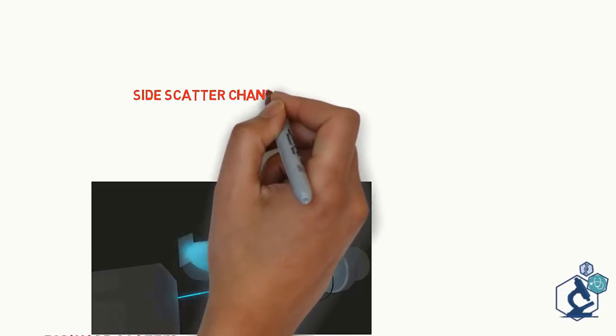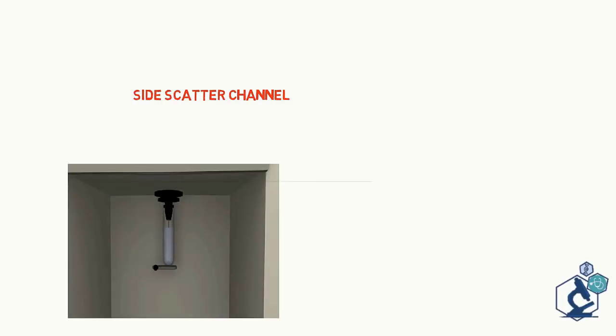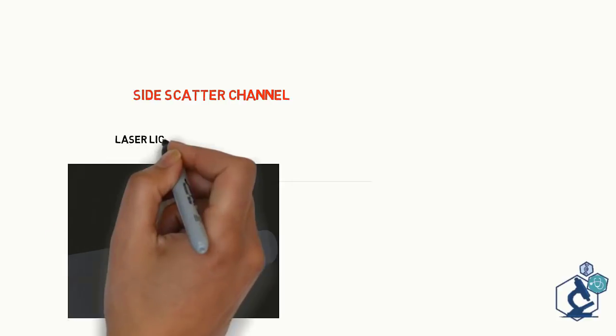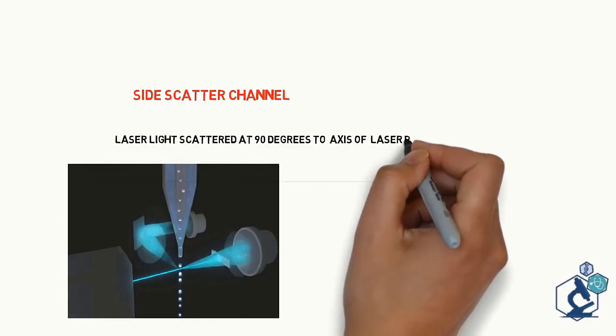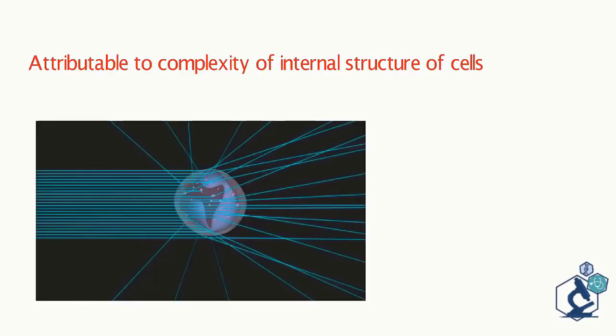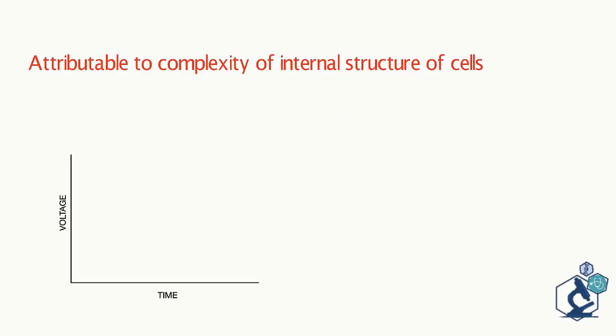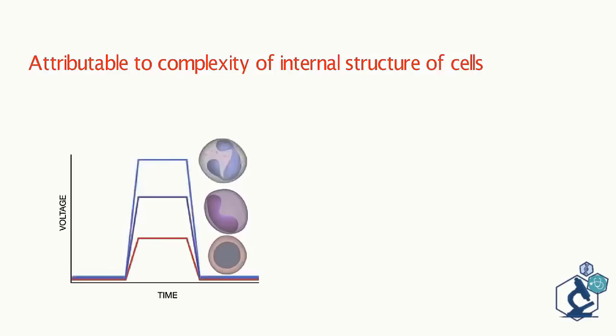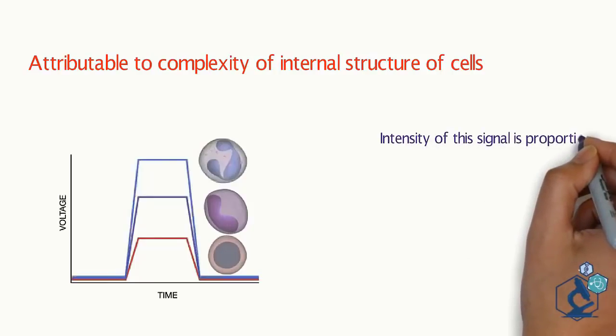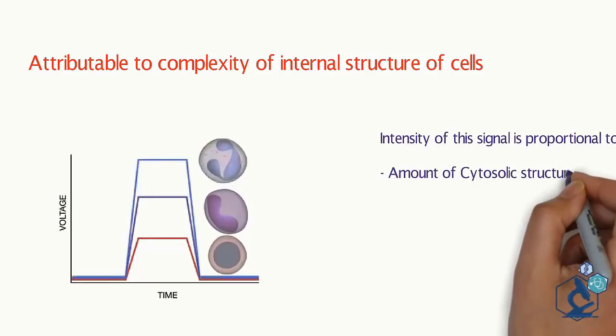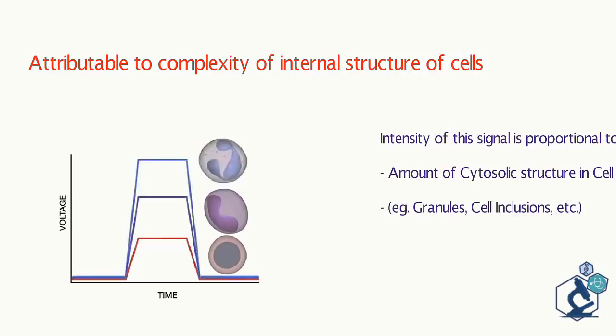The amount of side scattered light is detected by a detector located perpendicular to the path of the laser beam. Side scatter is proportional to the shape and internal complexity of the cell. Just like with forward scattered light, the flow cytometer converts the detected side scattered light into a voltage pulse which is directly proportional to the amount of side scattered light. Intensity of this signal is proportional to the amount of cytosolic structures in the cells such as granules, cell inclusions, vacuoles.